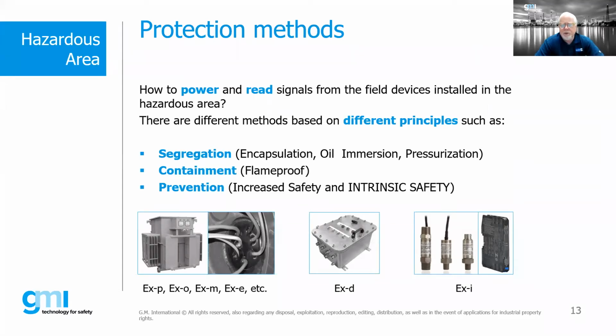a gas vapor oxygen combination get on the inside of an enclosure. One of the misconceptions out there in industry is flame-proof enclosures are somehow gas tight, and they aren't. They will actually allow gases and vapors if it's outside of the enclosure. Due to normal heating and cooling, we're going to have this constant movement of gas and vapors from the outside to the inside and vice versa. So flame-proof is containing an explosion on the inside and making sure that doesn't propagate to the outside and cause more damage. And then finally, there's prevention, and that's where increased safety and intrinsic safety come into play.